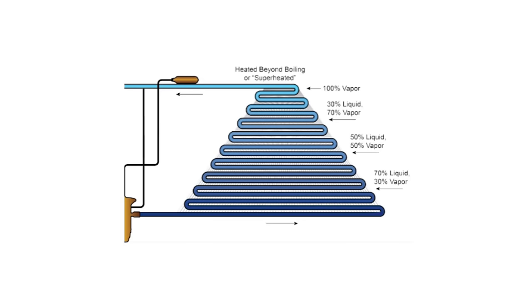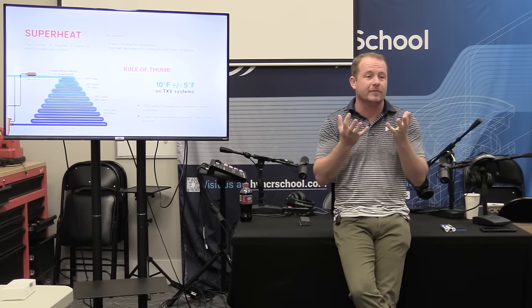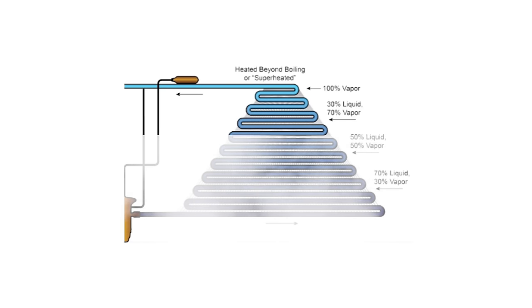How would we define that? Look at the image on the screen. We don't always have TXVs though. A TXV is one type of metering device option, so if we have a TXV, it does tell us about the function of the TXV. But I want to get even more to the root of what it is. Superheat is a measurement of how full the evaporator coil is with boiling refrigerant.